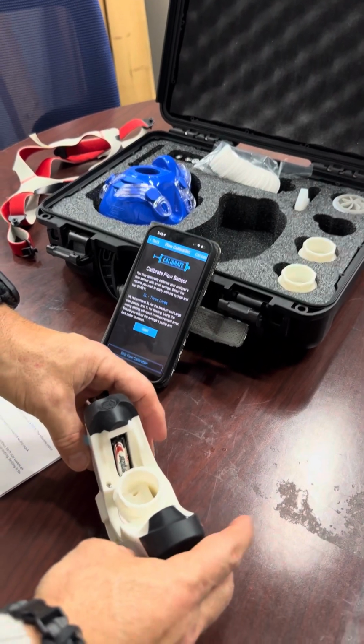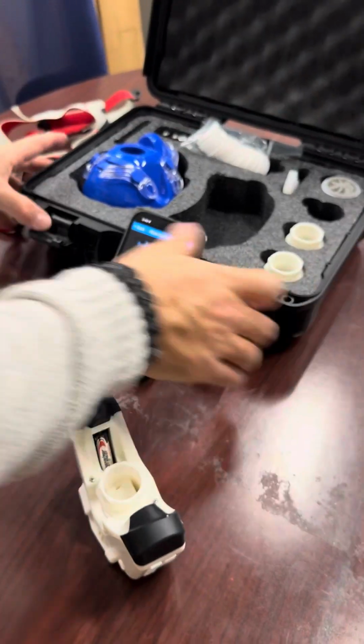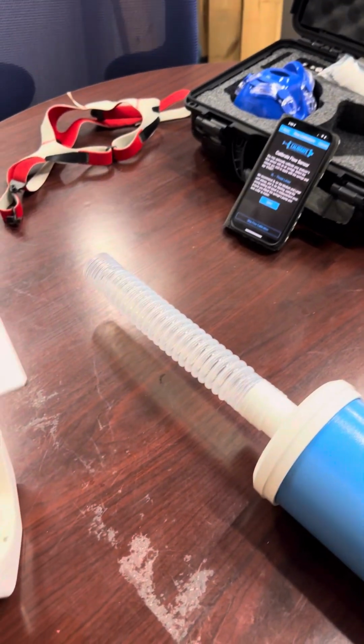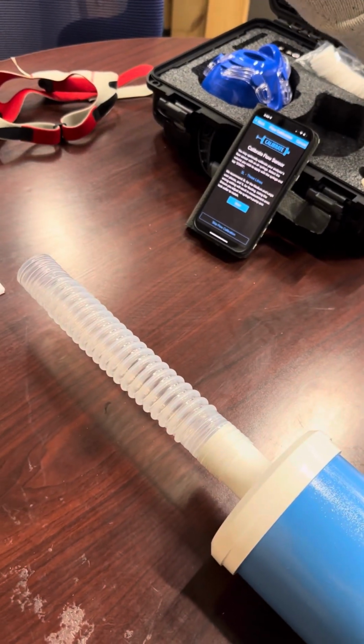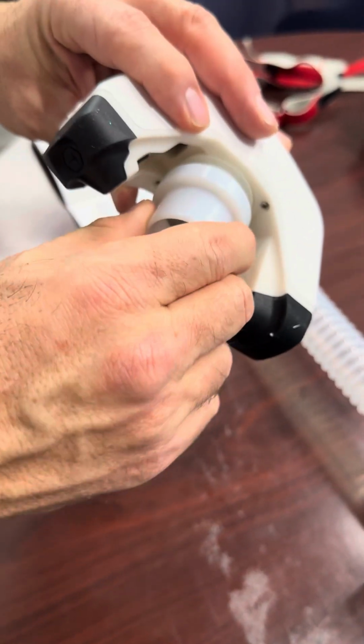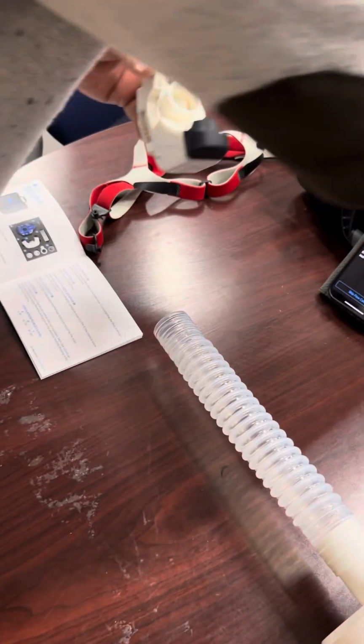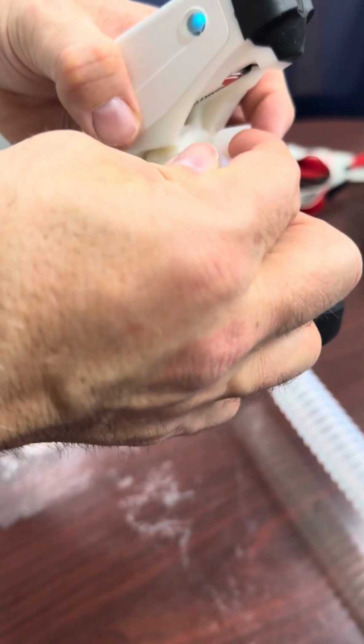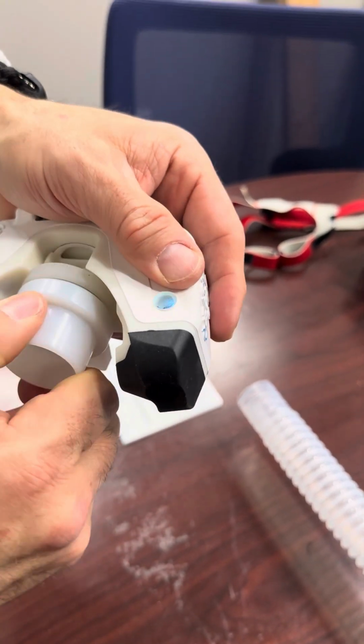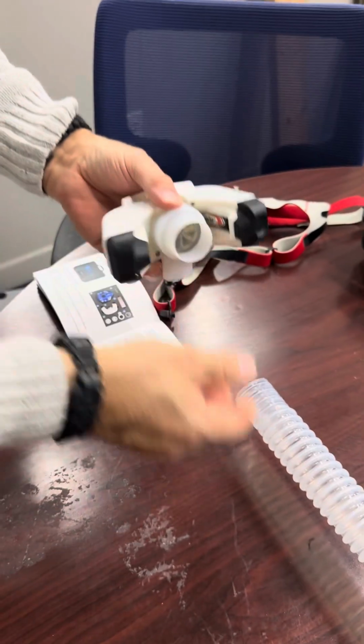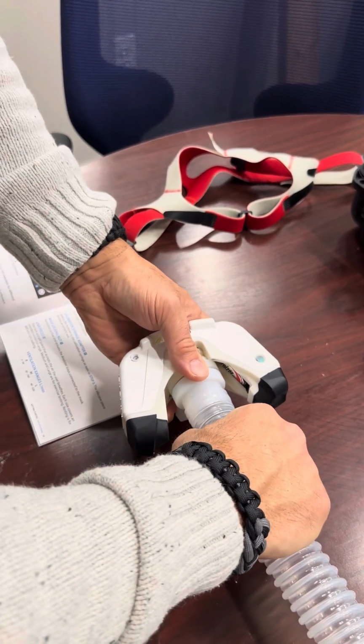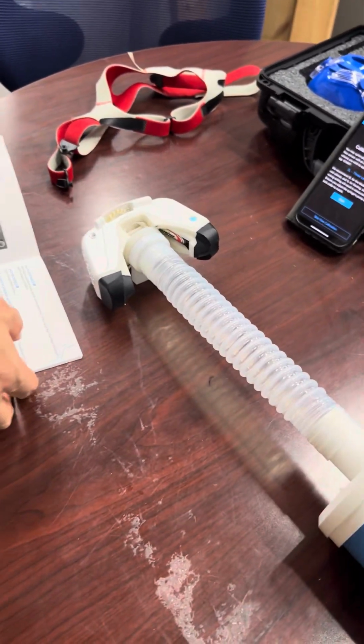Next part, we want to make sure the syringe is ready. We're going to move this out of the way for a second. We put the syringe piece on here. And then we're going to get the syringe adapter, which is at the top here. It fits right in and it just twists. But first, before we do that, we're going to put this piece in here, and we want to have this so it faces in a downward direction like this. So this is the top of the VO2 Master, and this is our piece, and we want to make sure the extra bulk piece is towards the top, so it looks like that. Next, we want to put in our syringe adapter piece, screw it in so it's in there nice and tight. And then we want to put it right on the syringe piece, or the syringe hose. Having a hard time with words here.